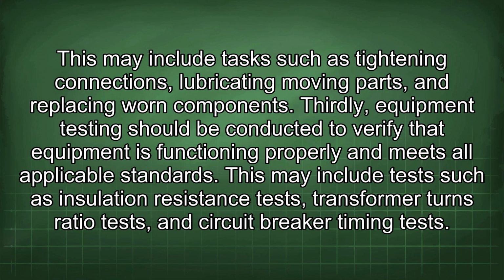This may include tasks such as tightening connections, lubricating moving parts, and replacing worn components. Thirdly, equipment testing should be conducted to verify that equipment is functioning properly and meets all applicable standards, such as insulation resistance tests, transformer turns ratio tests, and circuit breaker timing tests.